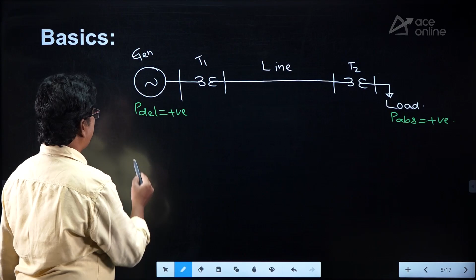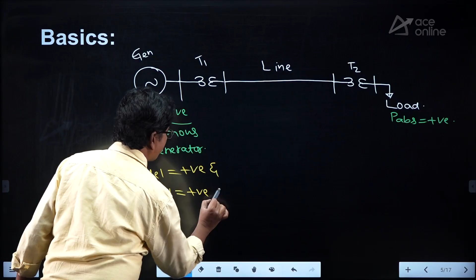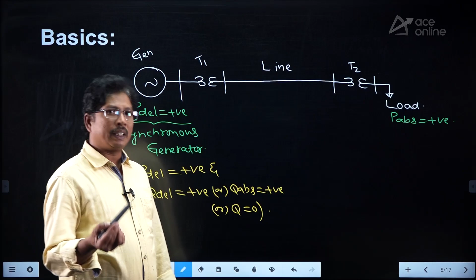The synchronous generator can deliver both active power and reactive power. It can deliver some positive value of active power, and it can have delivering capability of reactive power also, or absorbing capability of reactive power also, or it can have zero reactive power also. We know that synchronous machines have excitation to control, based on over excitation, under excitation or normal excitation. They can have delivering capability of reactive power, or absorbing capability, or zero reactive power capability also.